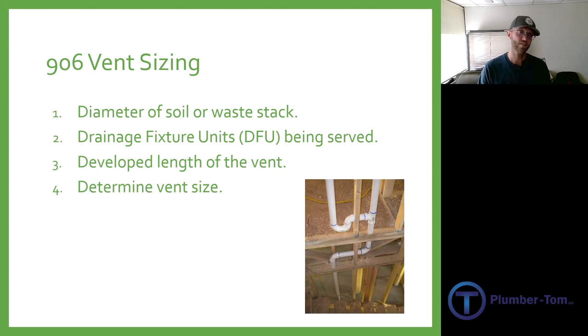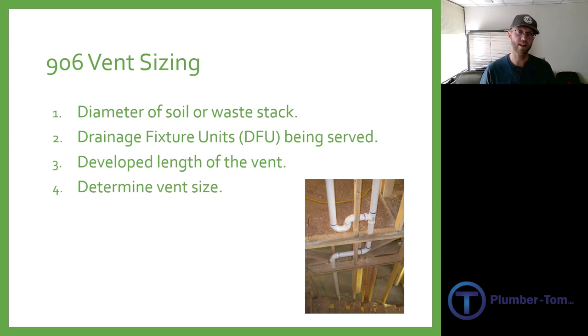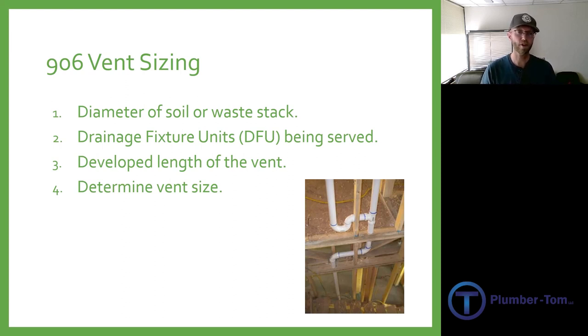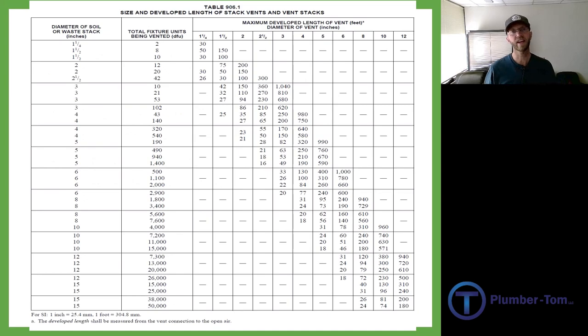Let's get into the step-by-step process for sizing of a vent. These steps are not detailed one through four in the code, but it's all implied. Here's what you need to know in order to use the vent sizing table in 906.1. First, you'll need to know the soil or waste stack size — the pipe size of the drain. Number two, you need the drainage fixture units being served, since a drain pipe can serve a variety of drainage fixture units. Number three, you need a developed length — the length of the pipe. With that information, you can determine the pipe size on the table.